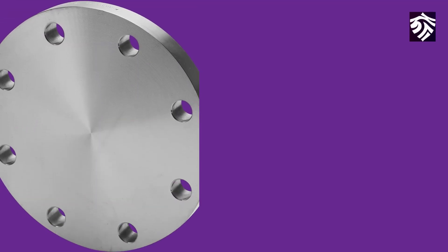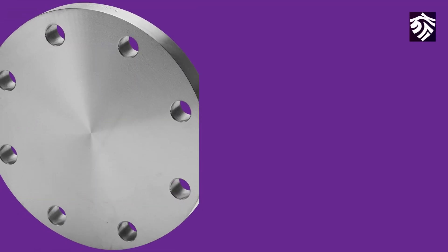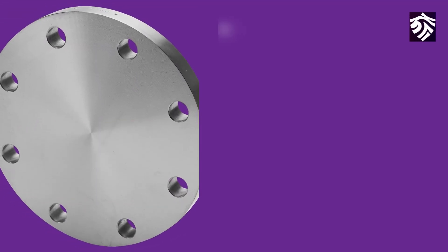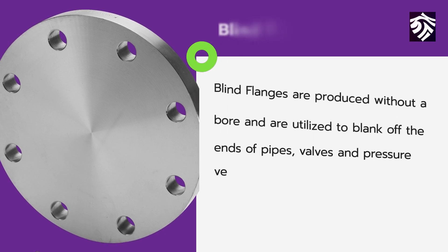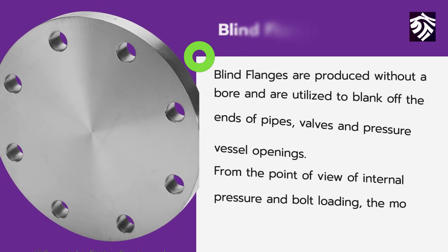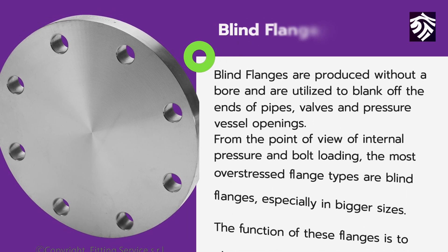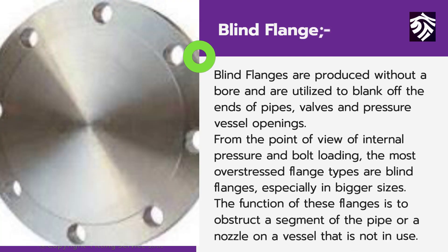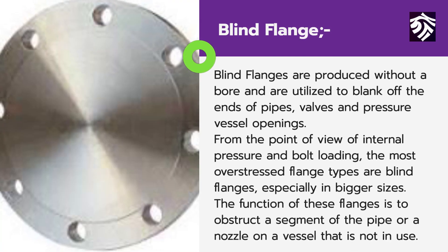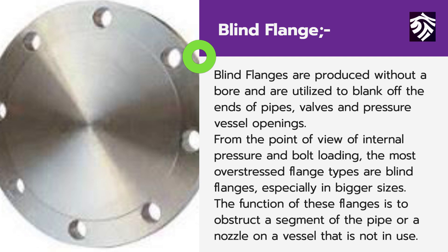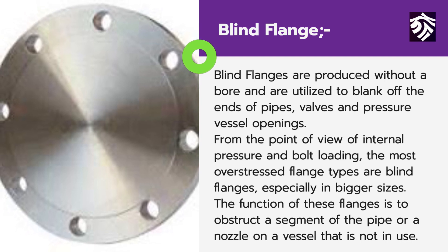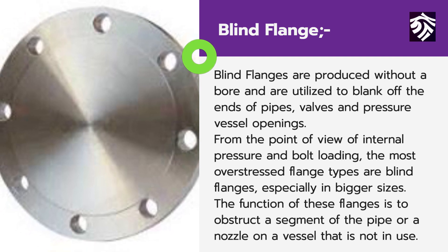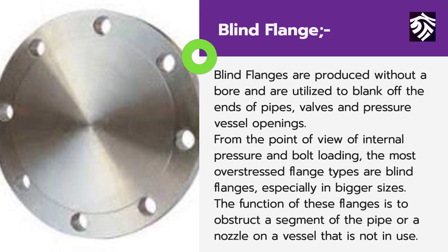Blind flanges are produced without a bore and are utilized to blank off the ends of pipes, valves, and pressure vessel openings. From the point of view of internal pressure and bolt loading, blind flanges are the most overstressed flange type, especially in bigger sizes. The function of these flanges is to obstruct a segment of the pipe or a nozzle on a vessel that is not in use.